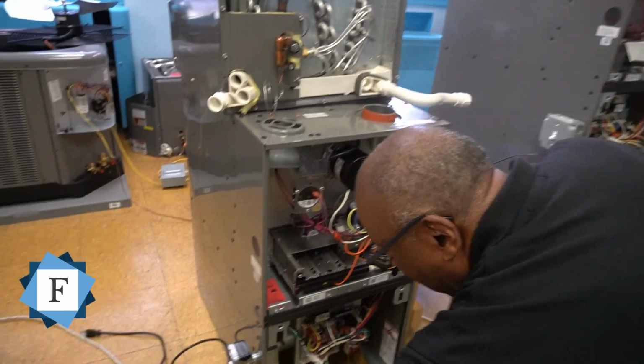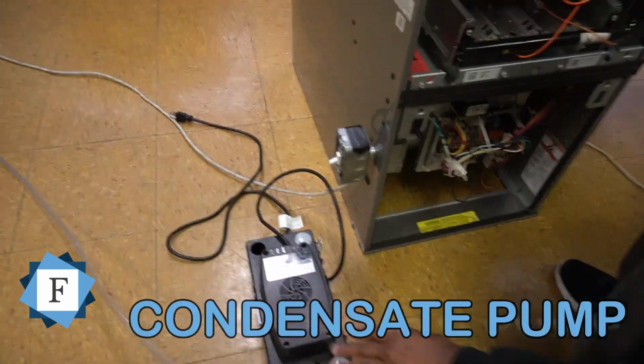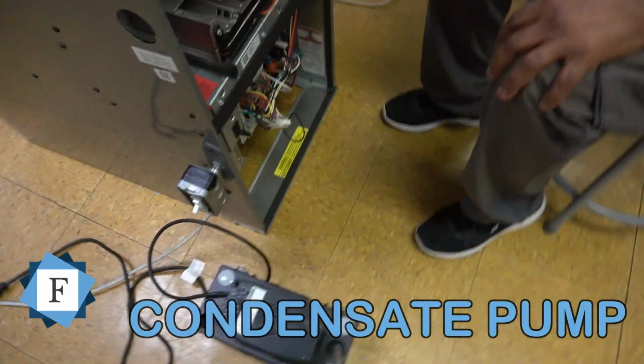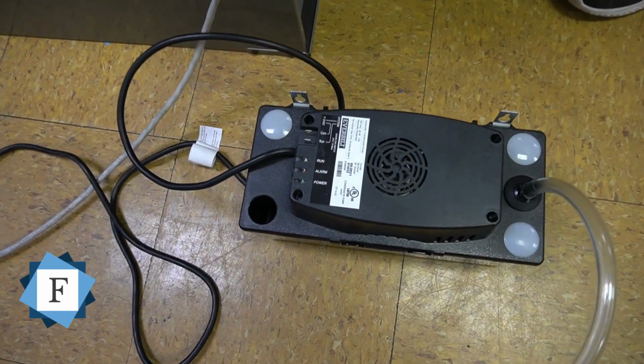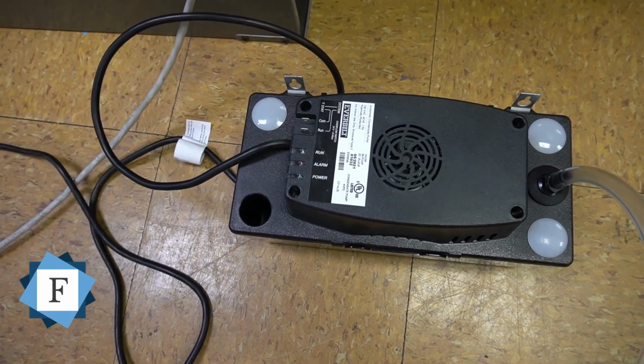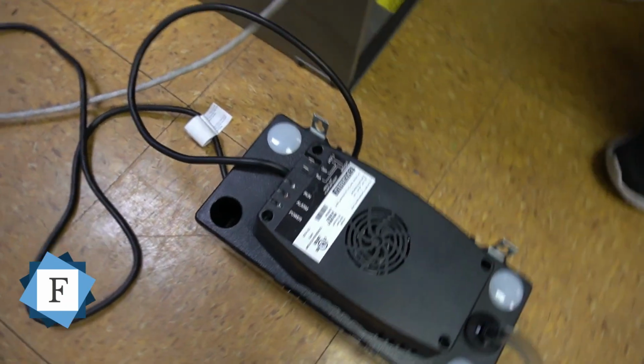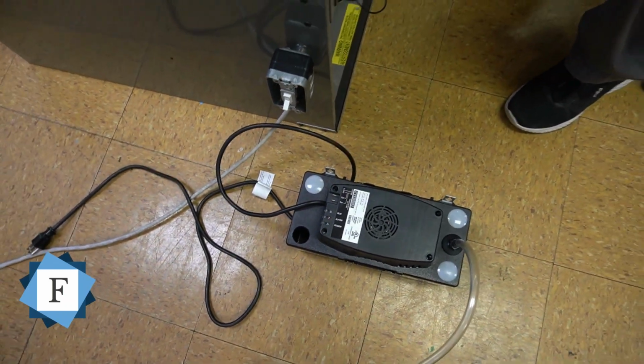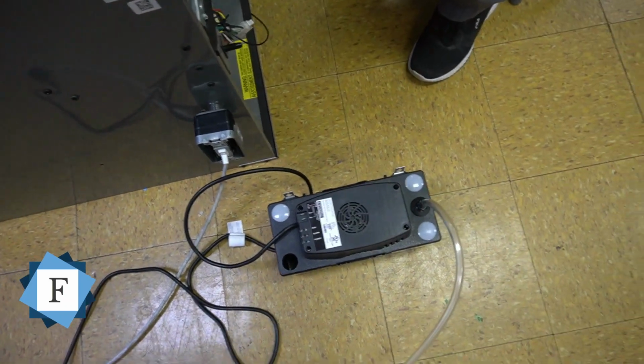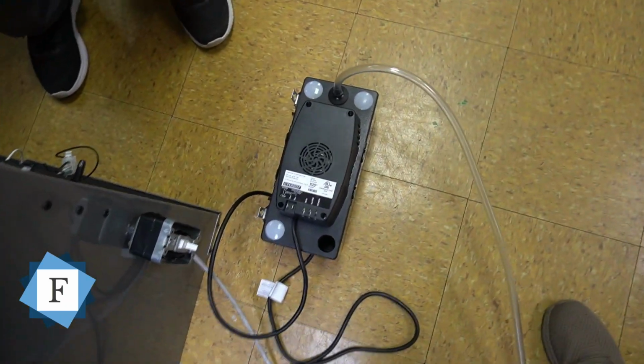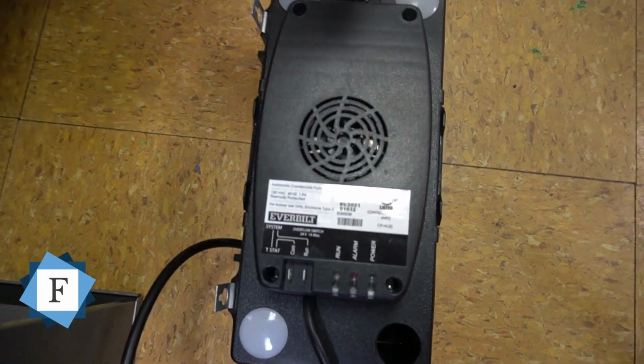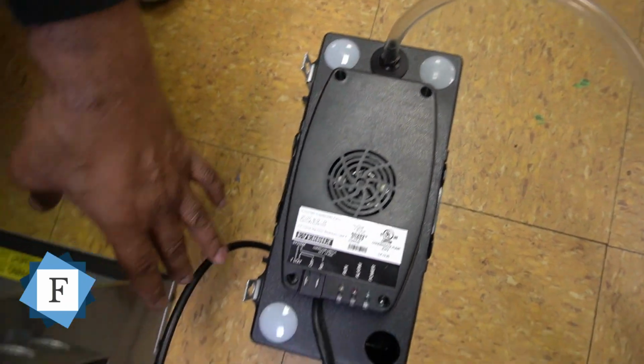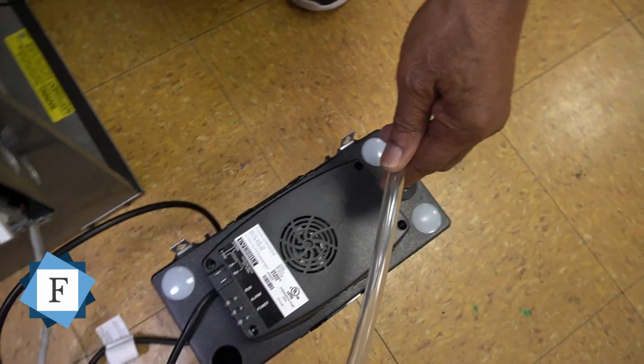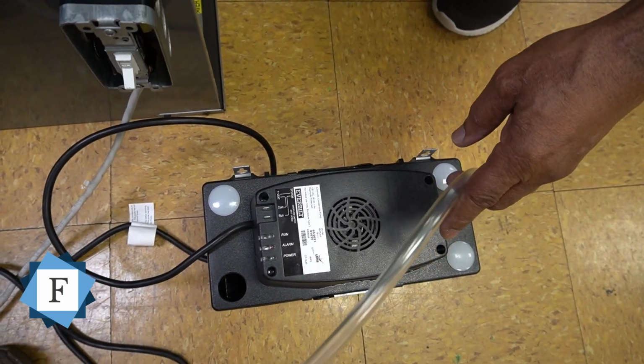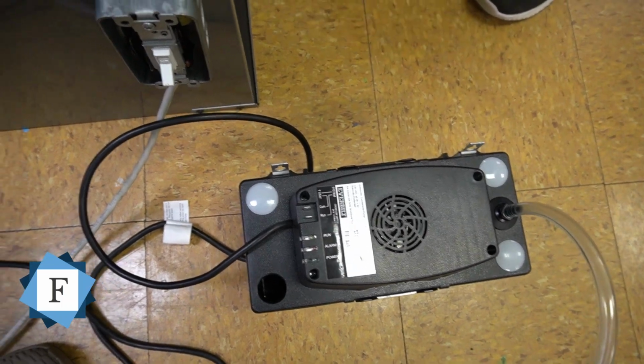And as you go, we also want to introduce our condensate pump. If you have an air conditioning unit split system, you must have a condensate pump. If you don't have a condensate pump, then you may have a drain line right at the unit where the condensation comes out of the evaporator. But if not, you have to use a condensate pump where it's plugged in, and this is where it discharges either outside or at a sink or wherever you divert it goes.